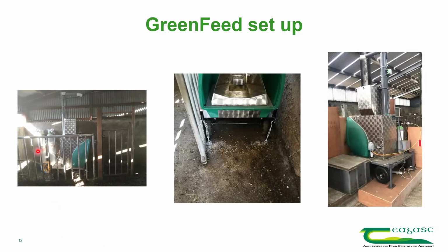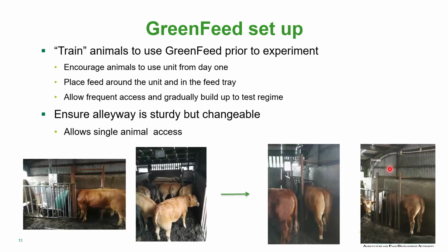Again, this is just the backside that we had of the unit here to allow us to perform our calibrations. The unit will obviously need to be protected from the animals, which goes without saying, but it also needs to be strapped down to the ground, so that when the animals are using it they aren't shaking the unit and disrupting the sensors. The sensors can be quite sensitive to strong jerks and shaking. So we bolt the systems down into the concrete, both on the floor and on the back of the unit, to stop the unit from moving around.